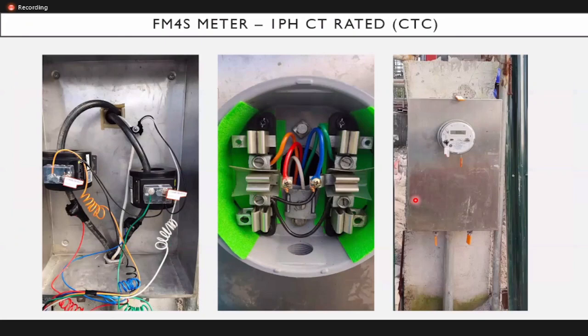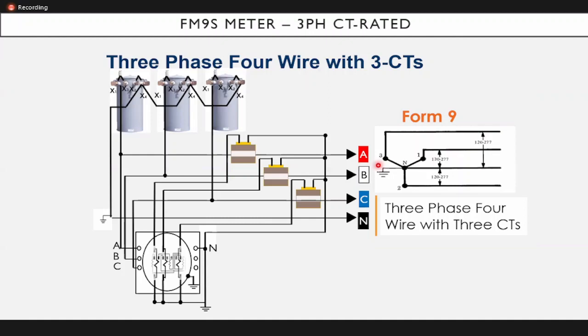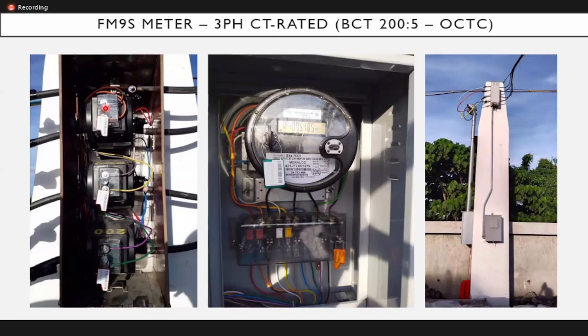This is another example in an underground setup. It's just the same. It's just that ang ginagamit pong current transformer cabinet niya is a little big, and this is the CTC. The three-phase four-wire with three CTs use form 9S. Ito po yun. We have three bushing current transformers or BCTs normally ranging from 200:5 using small OCTC, this one.